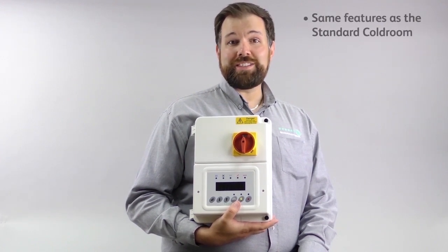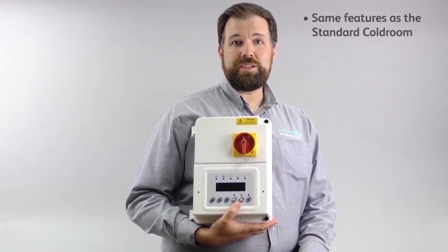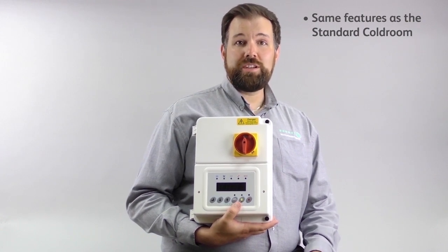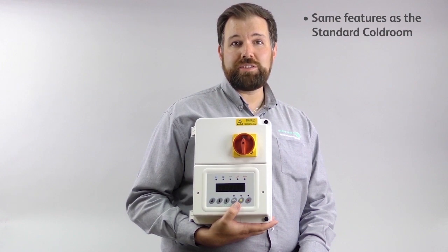It has the same great features as a standard Coldroom panel but with the advantage of driving a stepper expansion valve. Also included is a pressure transducer input for the calculation of superheat based on suction pressure.